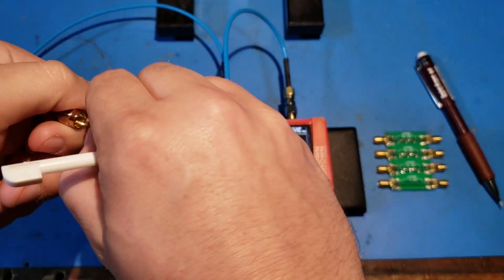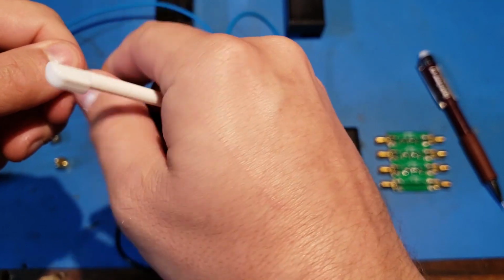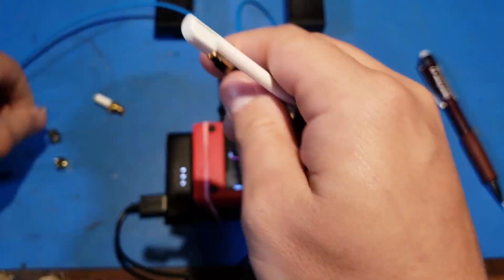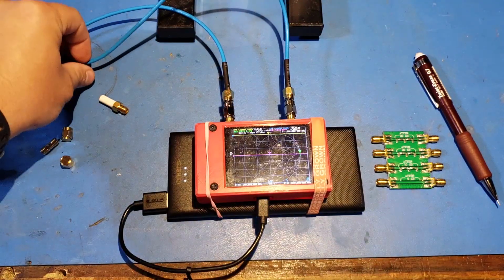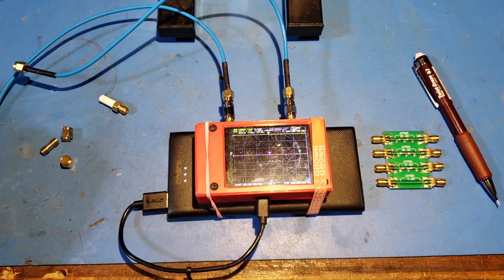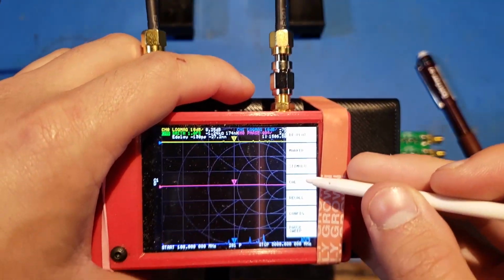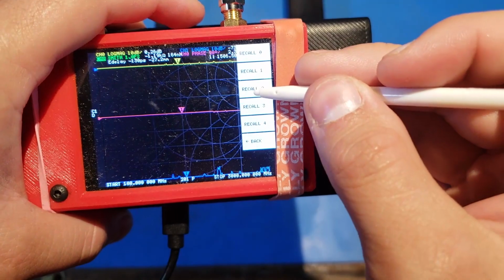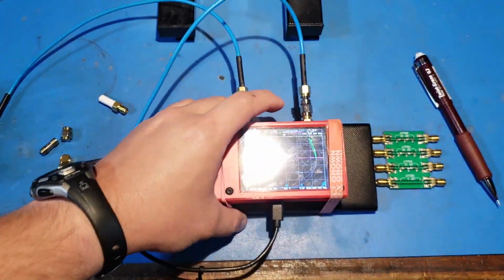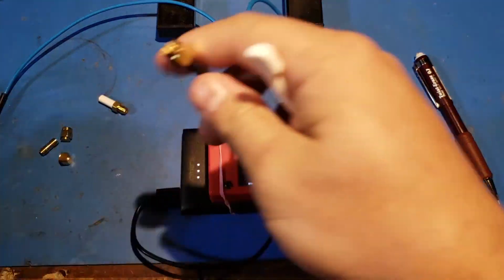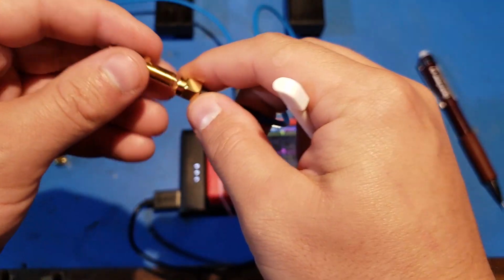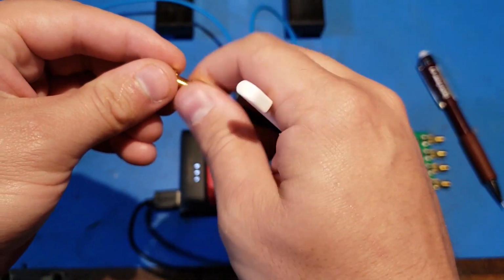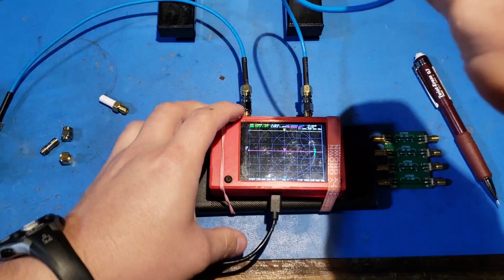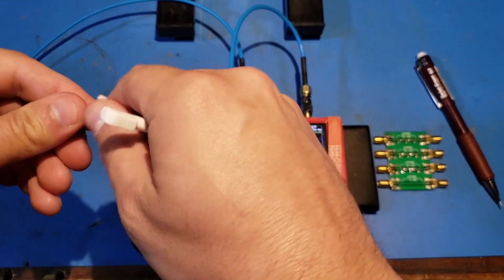And then for good measure we can check our new definition of an open, which is nothing connected to the male SMA port, and we see pretty much a dot on the right side of the Smith chart on the x-axis, so that's all looking good. Next up is to check our 1-port calibration of the female standard, so we'll recall calibration number 2, and then we connect our open circuit female standard here, and we should see a dot on the x-axis on the right side of the Smith chart, and we do.